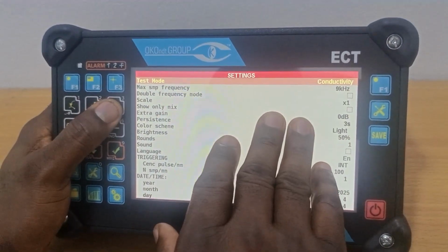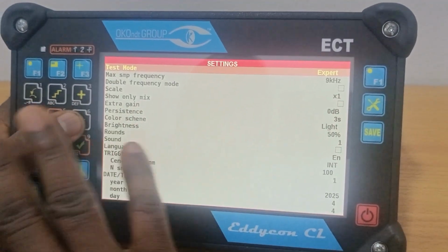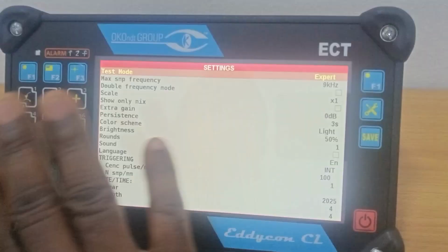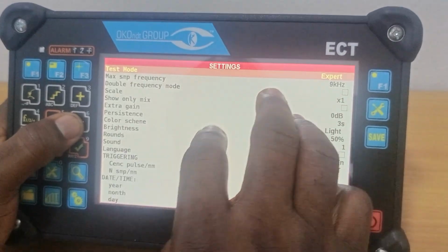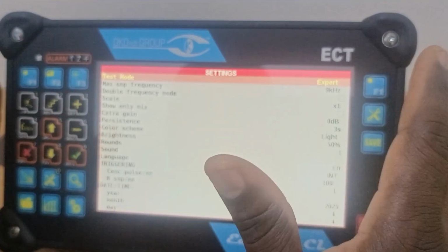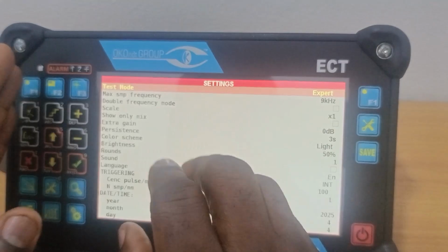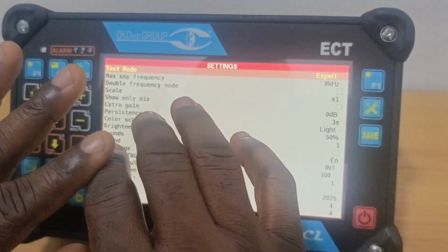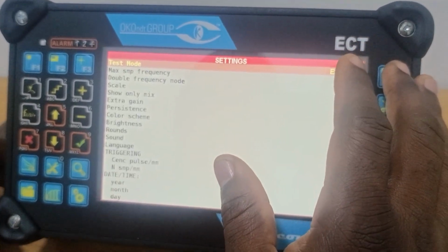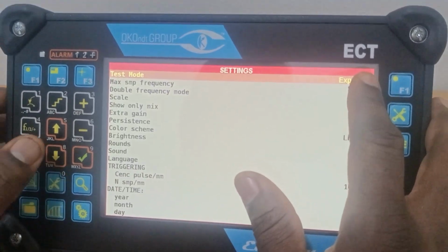Your expert mode covers your weld inspection, your surface inspection, your wheel inspection, everything. What this equipment functionality does is group all these applications where you are doing what we call flaw detection, whether you are looking for a subsurface crack or a surface crack, whether you are doing a wheel scan or a plane surface scan, they all fall under the expert mode.